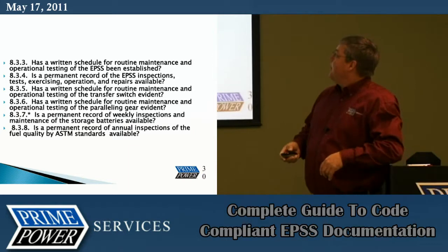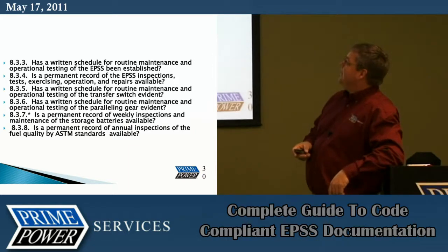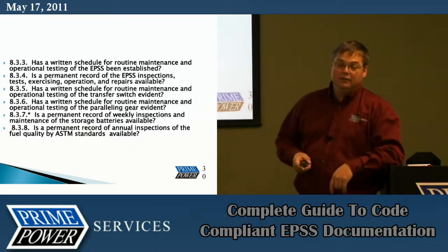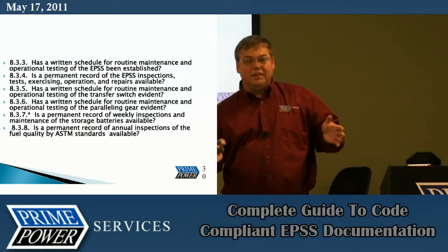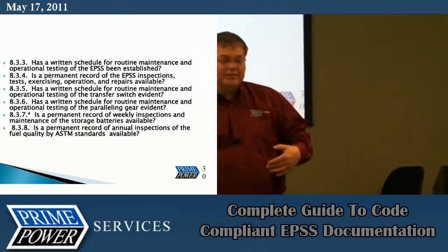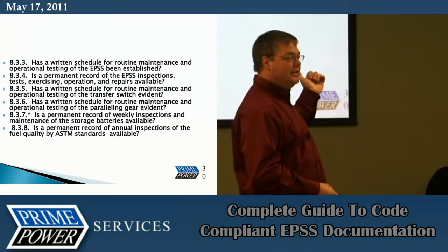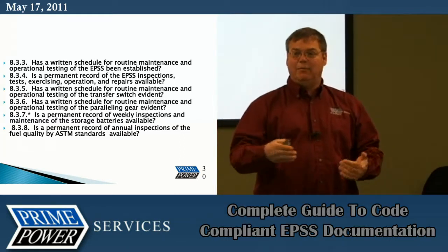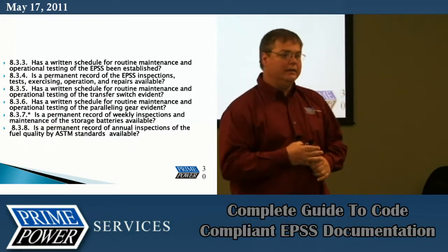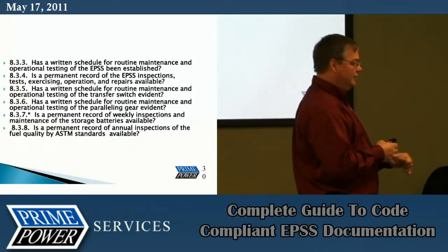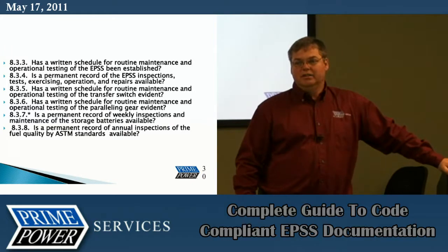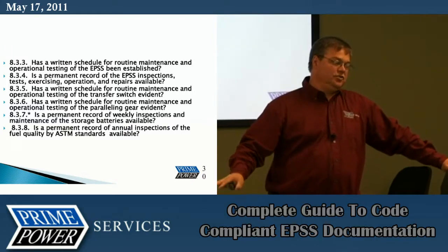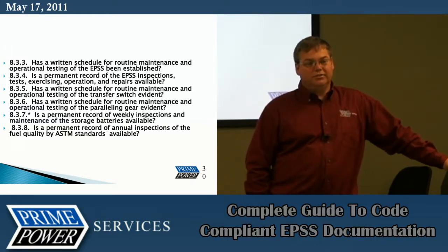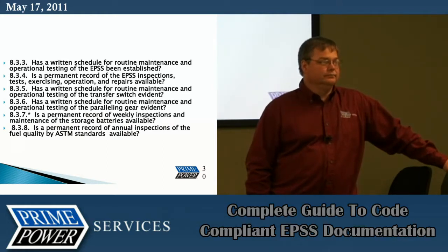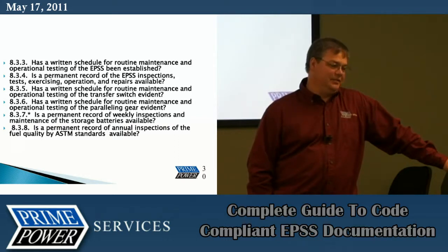Is a permanent record of the EPSS inspections, tests, exercising, operation, and repairs available? The documentation is required, not optional. It's in the standards and codes that a permanent record must be available for review. The codes vary on time frames for record keeping, but generally most codes say 7 years on maintenance documentation. If you keep a permanent record, does that mean hard copy, or can it be electronic?